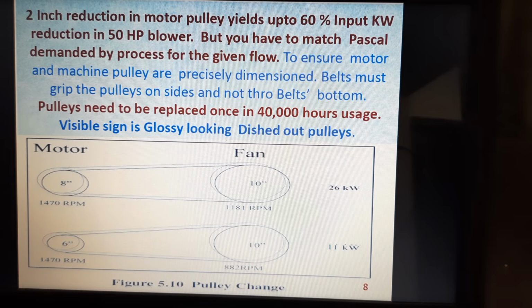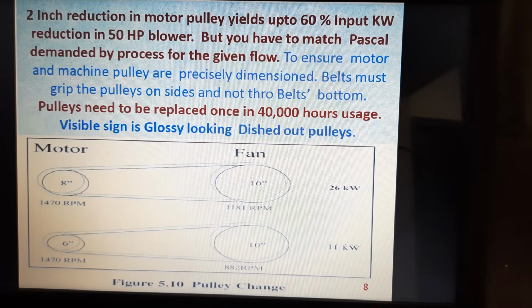Also, the pulleys need to be replaced after about 40,000 hours of usage. In many industries and buildings we find pulleys that have been working for more than a decade, but they need to be replaced every 40,000 hours, which is almost 5 years of usage. Visible signs in a pulley are a glossy look and a dished-out profile. These need to be removed immediately and replaced with a correctly matched, precision engineered pulley.